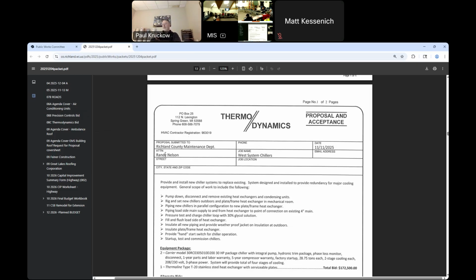I'm not too concerned about having a glycol loop. We do it all the time. Flowing to a stainless steel plate exchanger, a plate and frame actually, and then your load would run through the other side of that plate and frame exchanger. I'm a little concerned about having the new refrigerant indoors, because with propane-based refrigerants you're supposed to have a mitigation system if they leak. With the 2 package outdoor chillers, we have no refrigerant in the building, just running glycol in and out. I do have a couple of drawings of the basic concept here if somebody wants to look at them. I also have a couple of cut sheets on the Carrier chillers. The efficiencies on the chillers go all the way from 10.7 at part load up to 21. So they're staged.